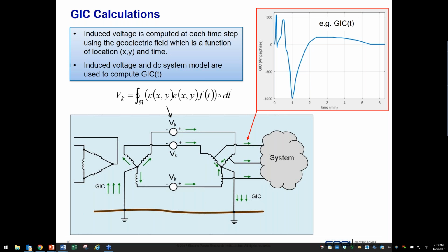And we basically found that we needed to take a time temperature analysis into consideration when looking at this system. So we went back and from manufacturers pulled the most conservative, most frequently used transformer designs in the United States, and we applied those time temperature curves to get an estimate of what would be actual transformer heating associated with those GIC currents. So you could think of it in this way.